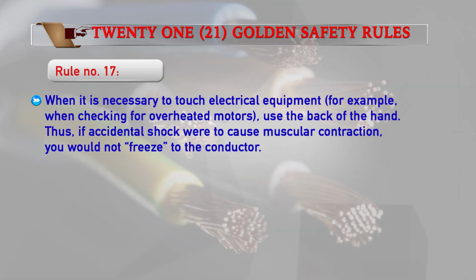Rule number 17: When it is necessary to touch electrical equipment, for example, when checking for an overheated motor, use the back of the hand. Thus, if accidental shock were to cause muscular contraction, you would not freeze to the conductor.